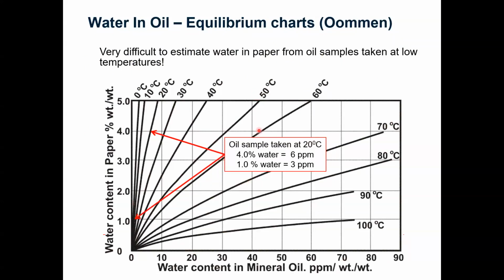And there is one more thing to mention. If moisture content is estimated from oil samples, and the sample is taken at 20 degrees, for example, then there is very little moisture in the oil, and a small error, like for example here, an error of 50% or 3 ppm, may lead to an estimation of water content in cellulose from 1% to 4%, which is like going from a dry to a wet transformer, which is again not very good for decision making.